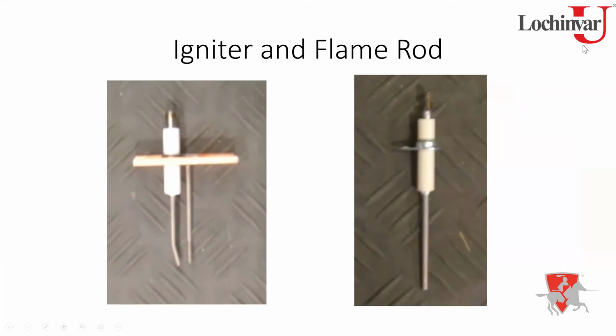All right, so igniter and flame rod. Now we've got burners, we've got gas, and we have to have something to light this thing with. This model is what's called a direct spark system. So we're not lighting a pilot, and I don't have a hot surface igniter here. I'm directly lighting the burner flame off of the spark. The control module sends roughly a 6 to 10,000 volt spark down to this igniter.